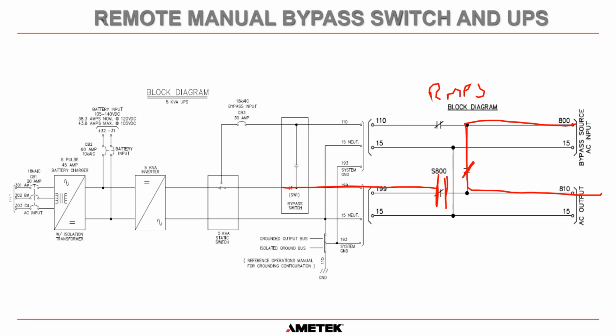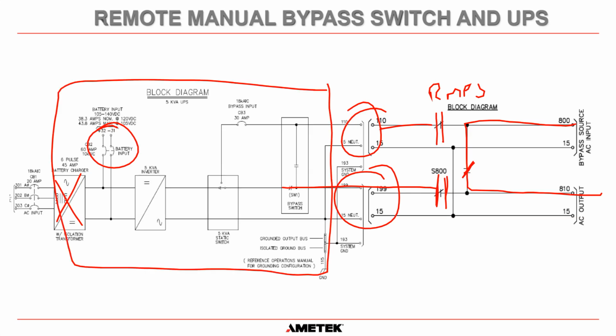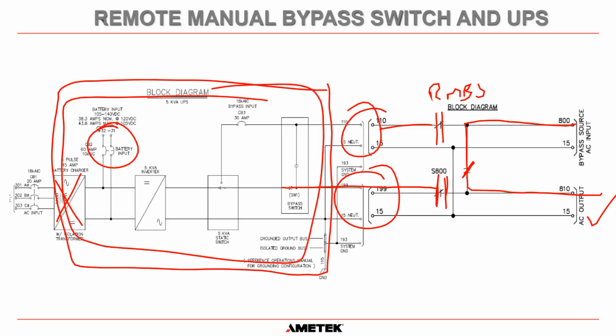Then you can move the switch to the bypass isolated position. That will open that contact, and then there's no power on these terminals. There's no power on these terminals. You can switch off the AC input there. You can disconnect the battery here, and in truth, you could disconnect all the cables. You could remove that UPS from service, and you could install a brand new UPS while the loads are still powered from your bypass source. So you don't have to take an outage if you have a system with an RMBS when you're replacing the UPS, and it also allows this system to be completely volt free to allow maintenance to be performed.